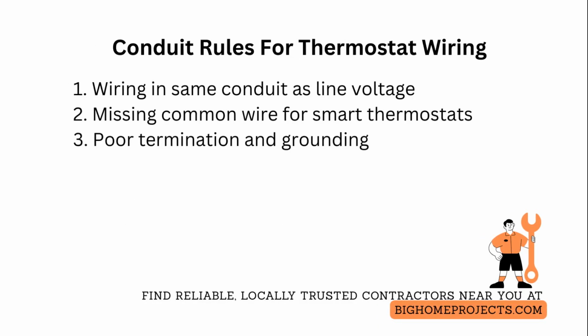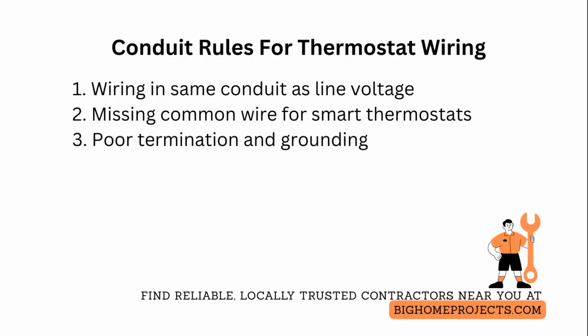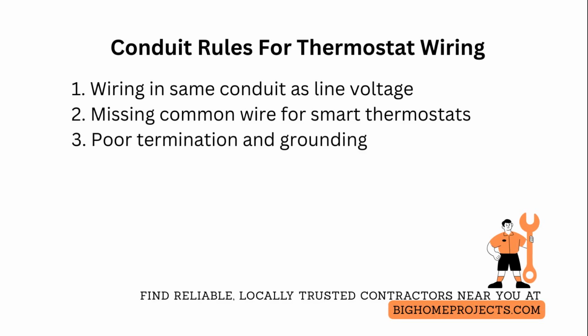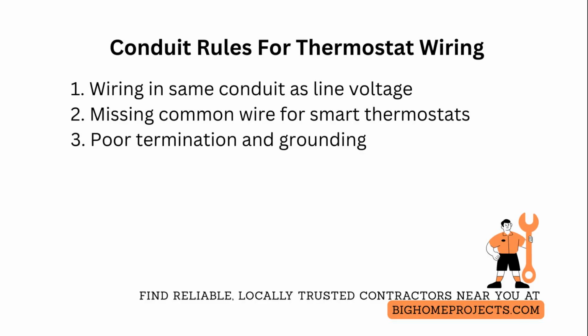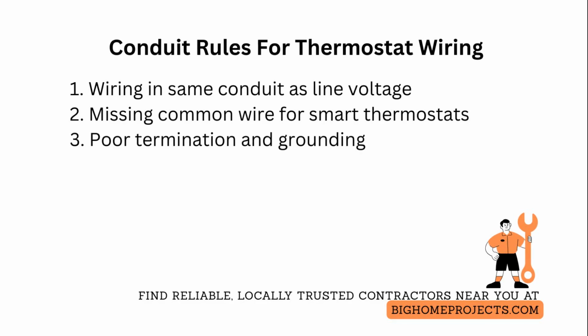One of the top 3 mistakes is thermostat wiring in the same conduit as line voltage, which causes electromagnetic interference and code violations. Fix it by separating low voltage control wiring into its own conduit or using a metal conduit as a grounded barrier, and follow National Electrical Code spacing rules and local amendments.